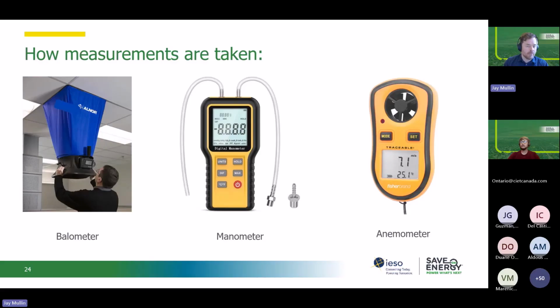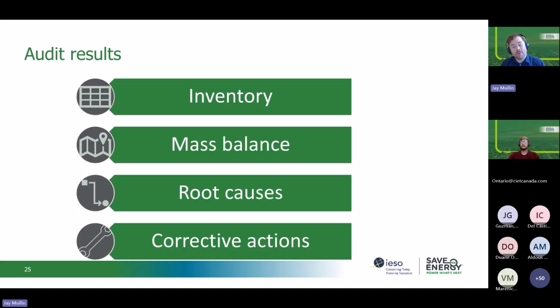And anemometers are also a really important tool to have in your toolkit for measuring airflow velocity, particularly at those capture points, to make sure that you are having the required airflow across those different openings as well. So these are often used in the air balance studies. And then from the results of the air balance studies, you often get that inventory of equipment. Where is all the air coming into the facility? What's all the equipment that's exhausting it? And that should show nameplate, actual flow, condition of all the pieces of equipment.